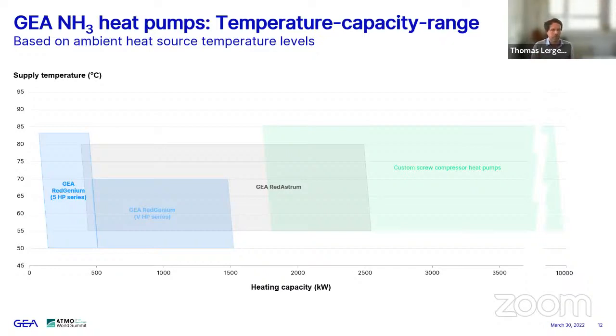There is a new development, which I'm very, very proud about, and we are very excited about this. This is a totally brand new compressor series, a reciprocating compressor series. It's called GEA Grasso VXHP, X for extra high temperature and extra large capacity. So this basically spans now open the temperature and capacity range with a very, very efficient piston heat pump. You can see capacities again up to nearly 2.5 megawatt, and now we can reach 95 degrees Celsius supply temperature.